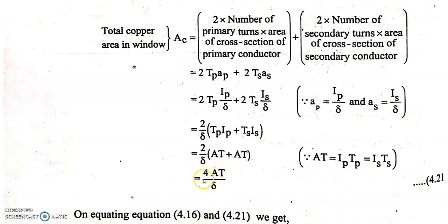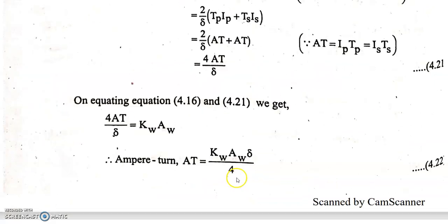So you just compare this equation. If we compare this equation for a single phase transformer, in a single phase transformer it will be 2 Aw by delta. So window and windings are added 2 times as compared to the single phase transformer in a 3 phase transformer. So it is 2 times of what we have obtained in a single phase transformer. That factor is verified now.